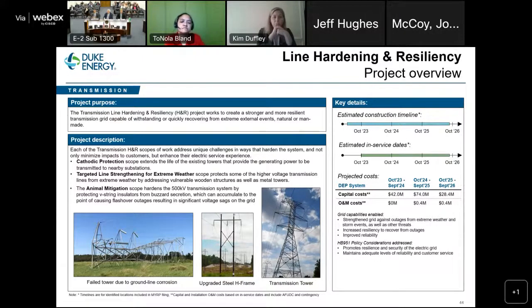The last one I'll mention is the animal mitigation project scope. This is a specific project targeted at our 500 kV system. One thing that occurs on the 500 kV system is that buzzards love to roost on 500 kV towers. You can see these as you're driving under systems down highways and certain areas past our largest transmission towers. Buzzards result in contamination directly underneath where they roost, and that results in flashover events. These flashover events are very significant on the 500 kV system, particularly impacting our industrial customers.